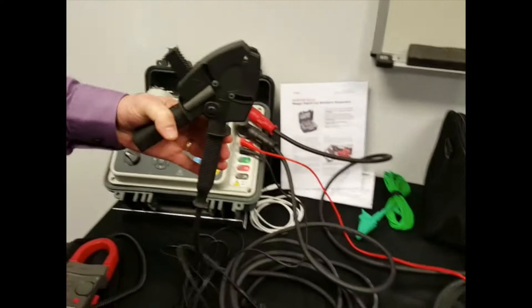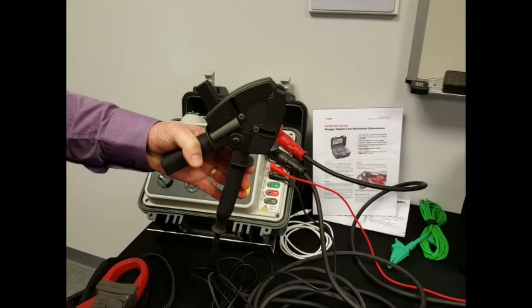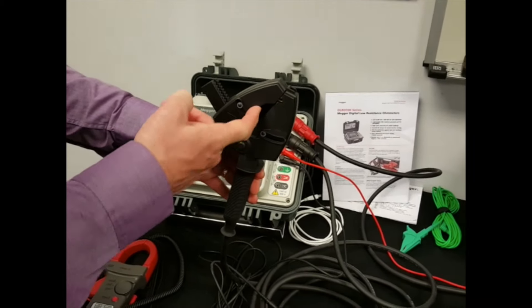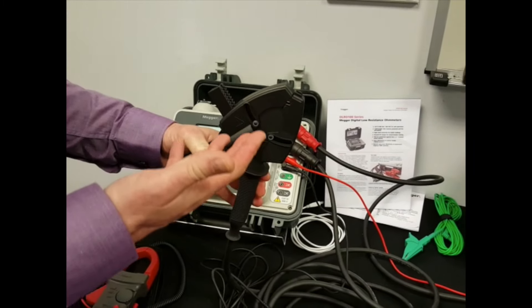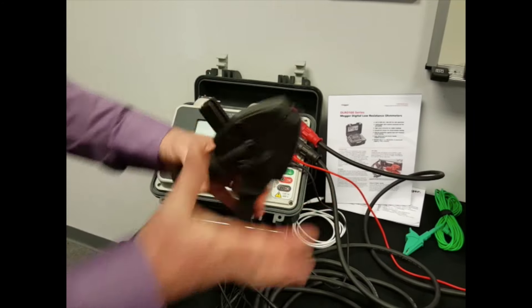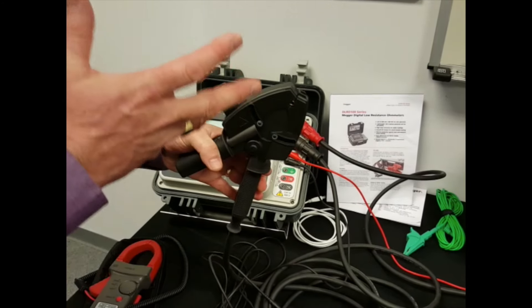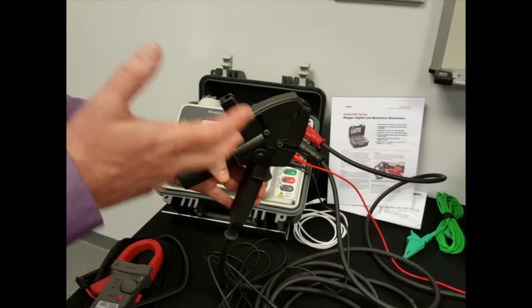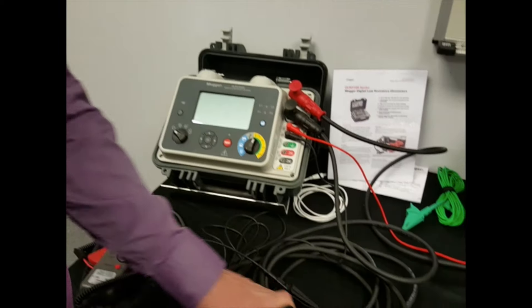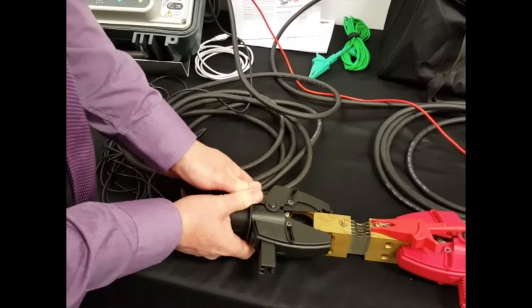These particular clips were designed specifically for the application. You can see it has shutters. So should this fall off a bus bar during test, this becomes completely insulated, which means you get rid of that hazard of an arc flashover. This is a unique selling point.